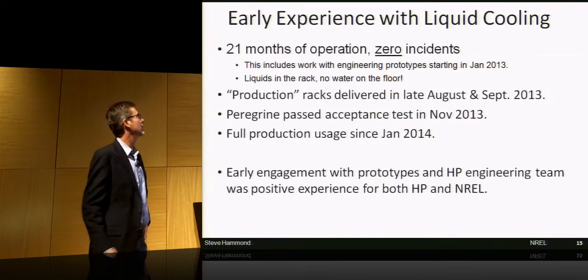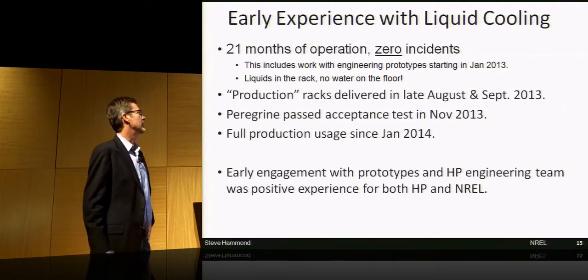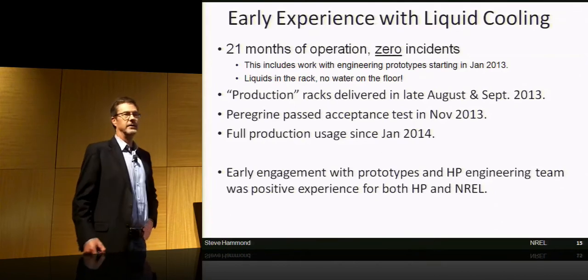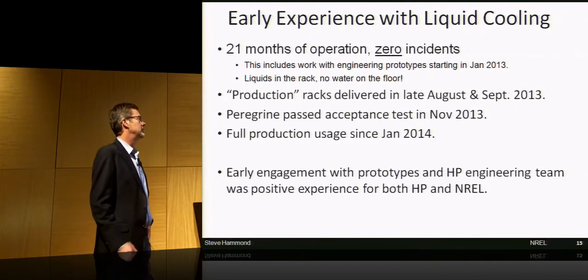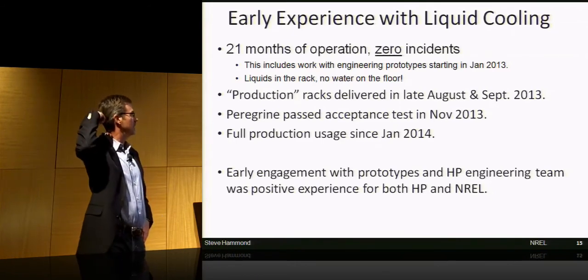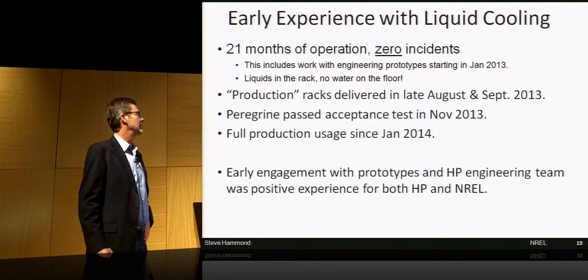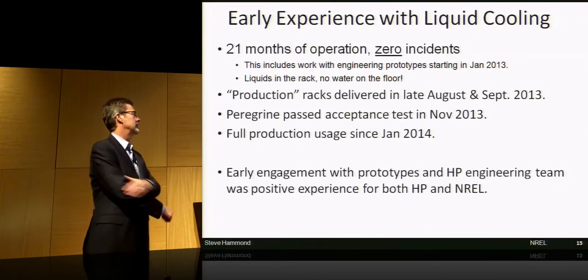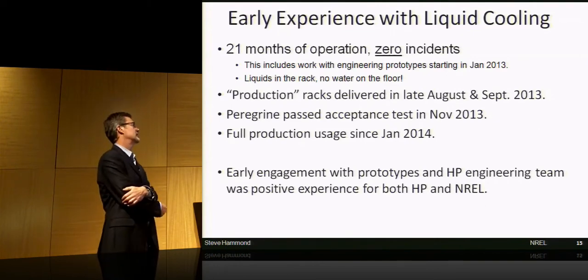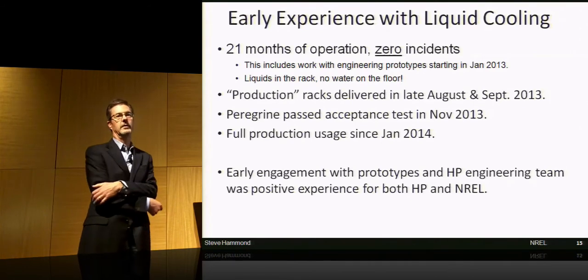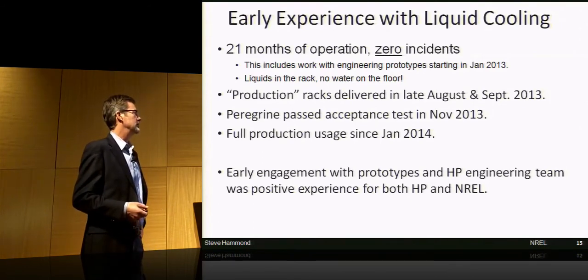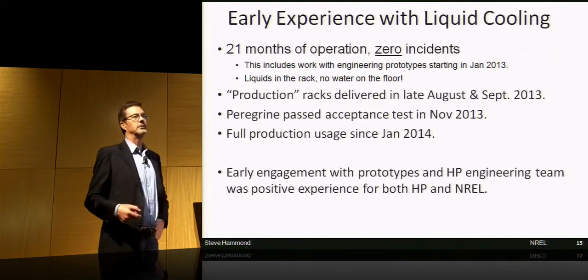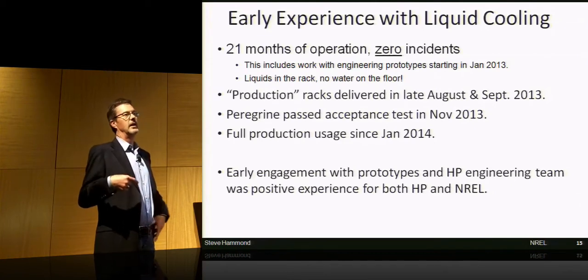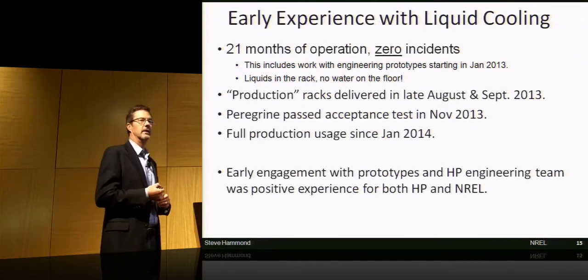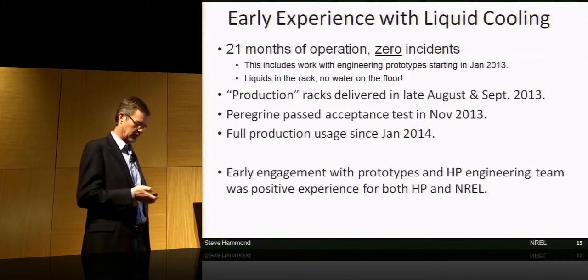Our early experience with liquid cooling: we've had liquid cooled systems for the last 21 months with 0 incidents. This includes our work with some early prototypes we got from HP in January of 2013. So we have liquids in the rack, but no water on the floor. Our production racks were delivered late August and mid-September of 2013, and our HPC system passed acceptance in November. We had 6 weeks of friendly user mode, and it's been in production use since 2014. We've had a lot of interactions with HP on how to design and interface the system with facilities, and I think HP would agree this has been a really positive experience for both organizations.